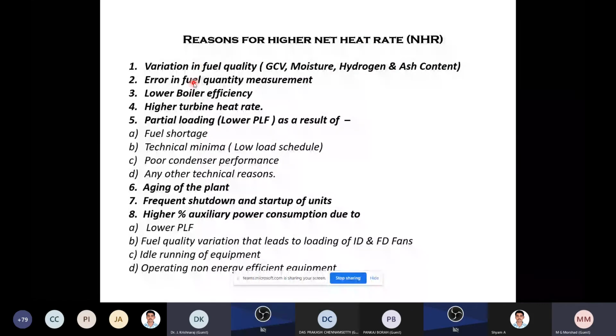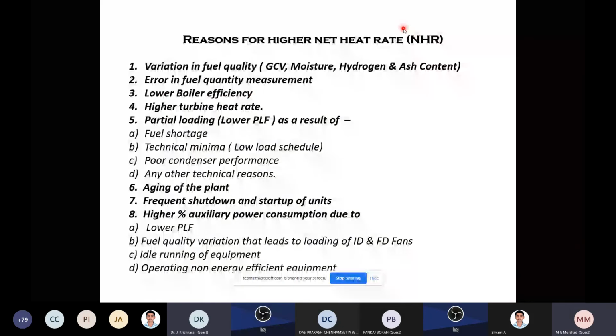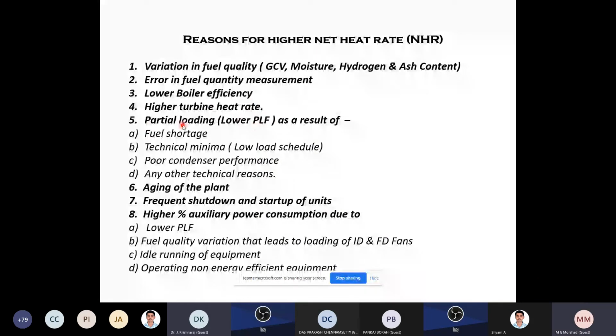Error in fuel measurement quantity. Suppose, because it is not 1 kg or 2 kg, the calculations are ton-wise. So if there is an error in the fuel quantity, then you can see the heat rate variation. Low boiler efficiency is also a cause for this. Higher turbine heat rate is also a cause. Partial loading of the unit also affects the net heat rate. Partial loading for what? Suppose there is a fuel shortage.